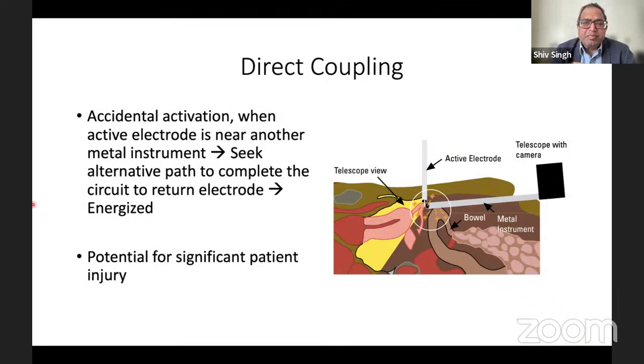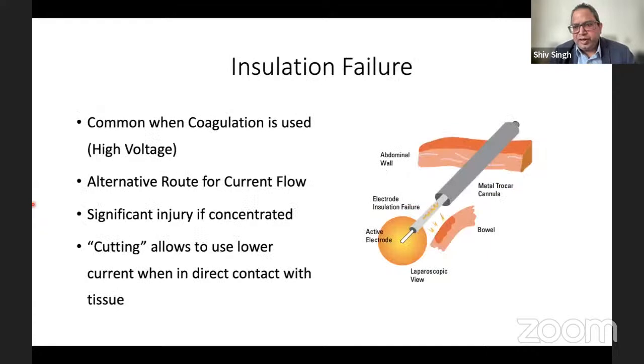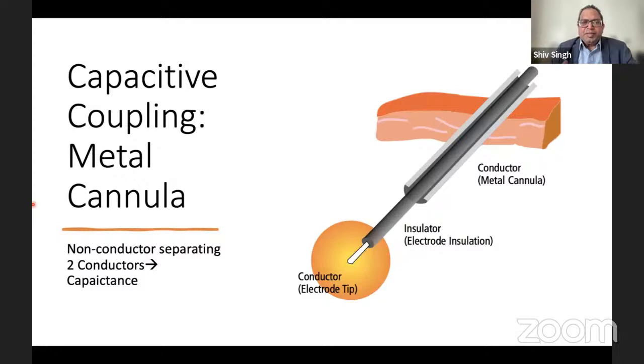And if it is touching an area other than what you want to cut or coagulate, that can cause, say, a bowel to get charred. Everything goes fine, the patient wakes up in recovery with abdominal pain and leakage. That can happen. So this was actually common. Same thing again with insulation failure. If there's insulation failure, there can be direct injury to the areas in contact with the diathermy. And there can be capacitive coupling as well.